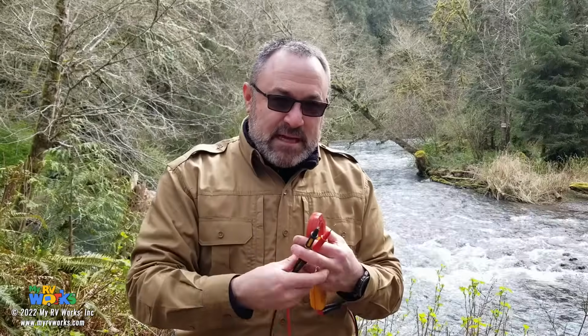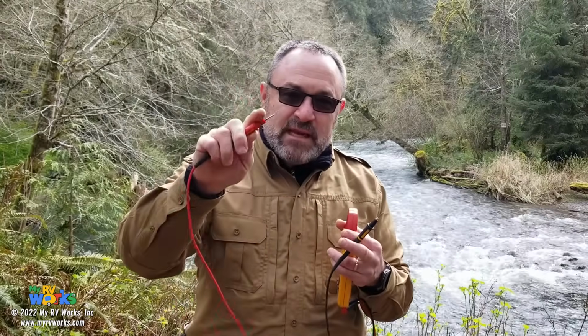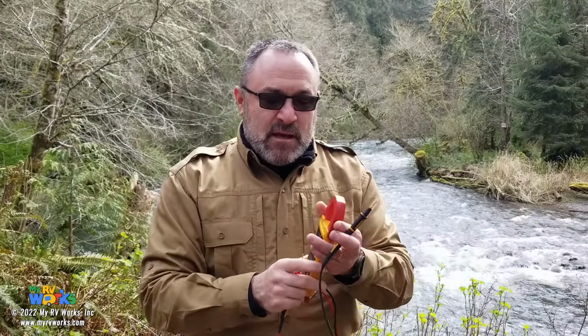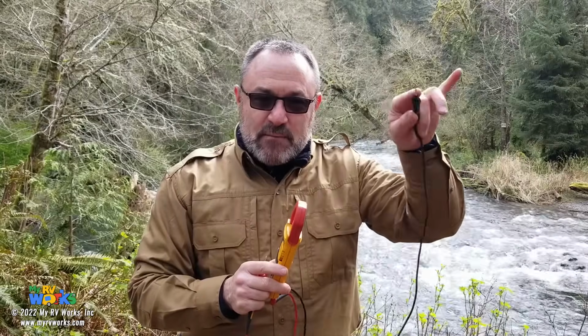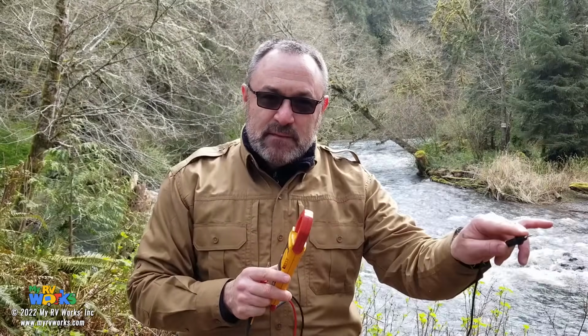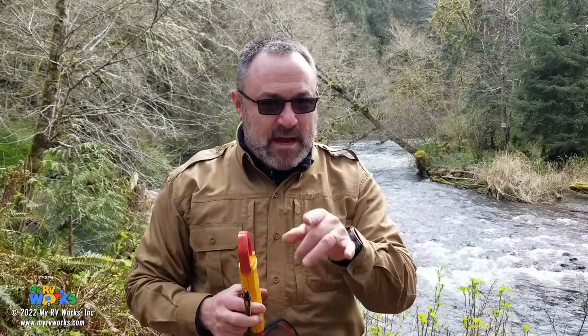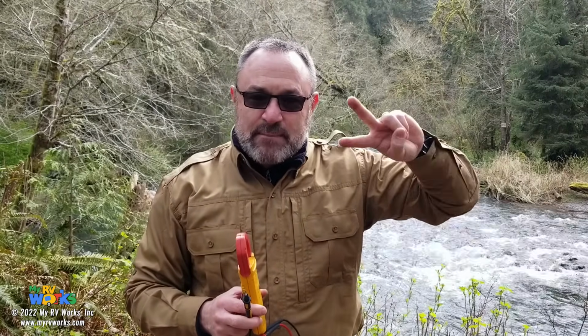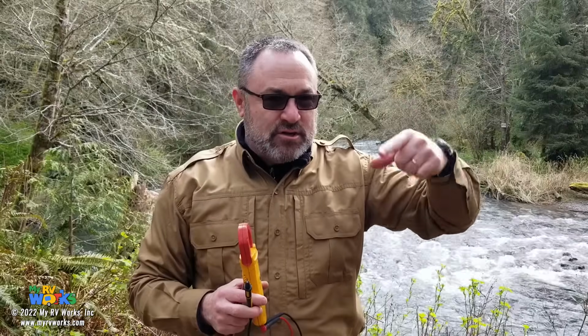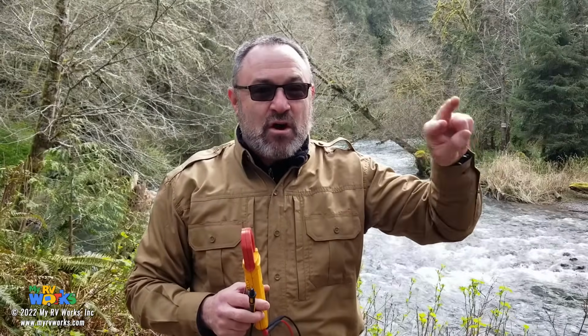But we're not done with our test yet. Still holding the red lead on the black wire, now move your black lead from the neutral to the ground. In an RV, this is different from a house. Your neutral and your ground should be totally separate - they should not be bonded.